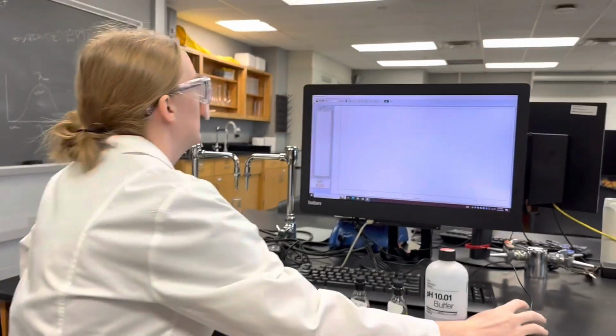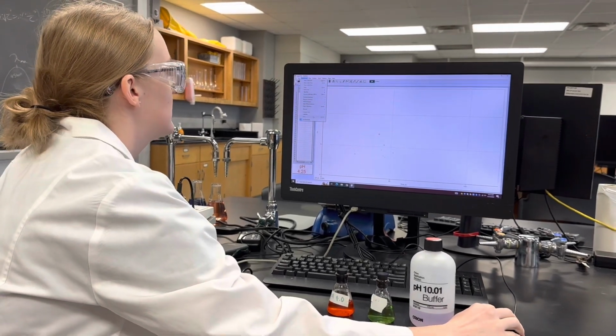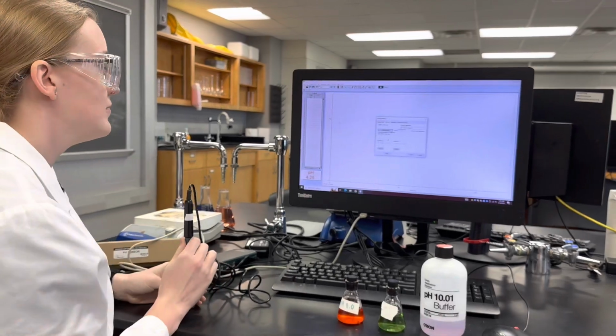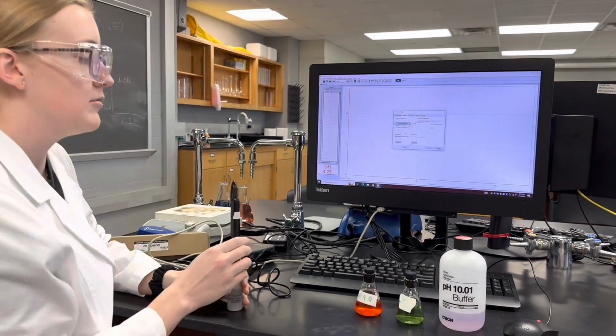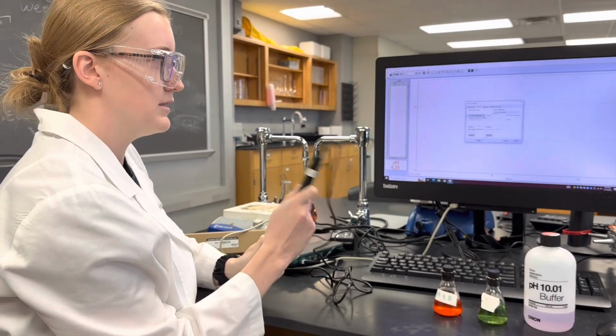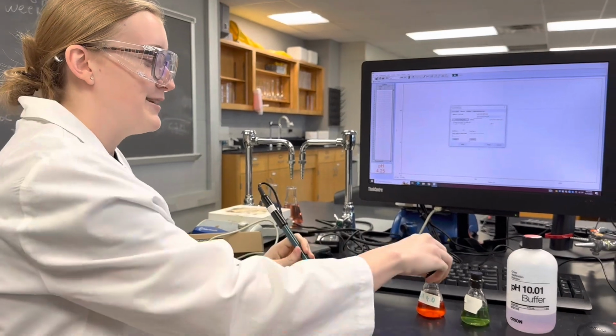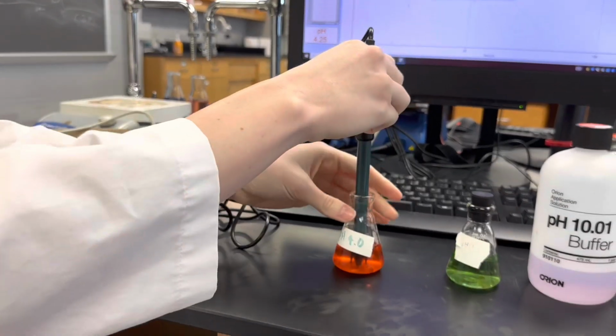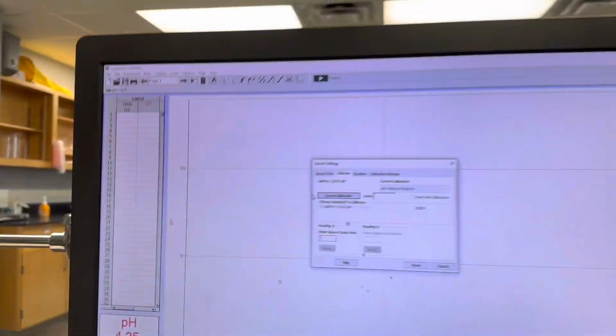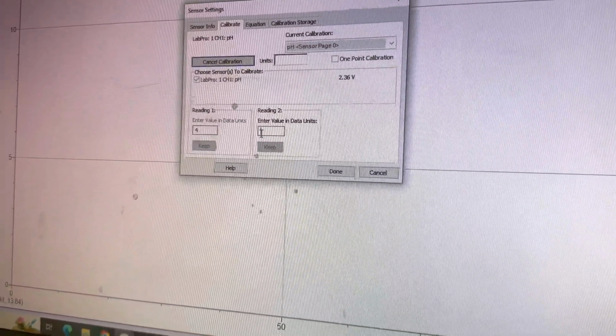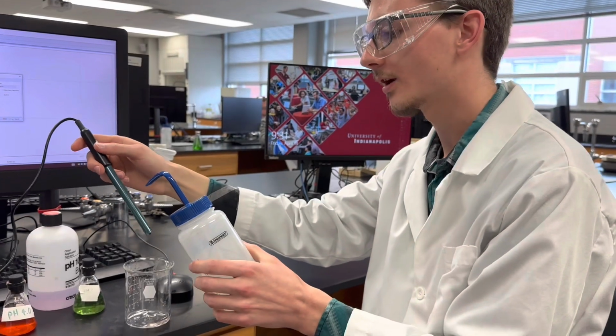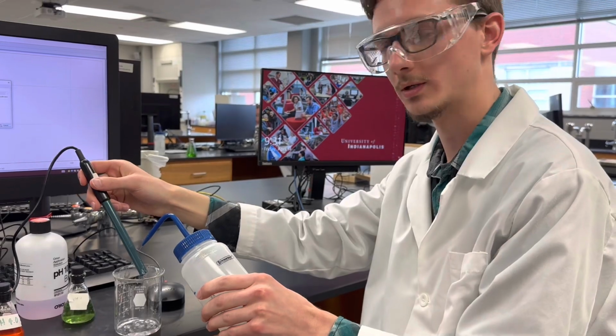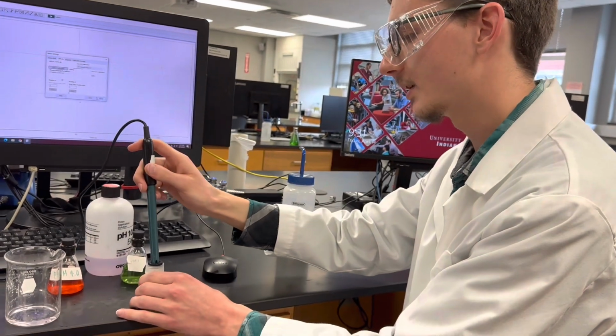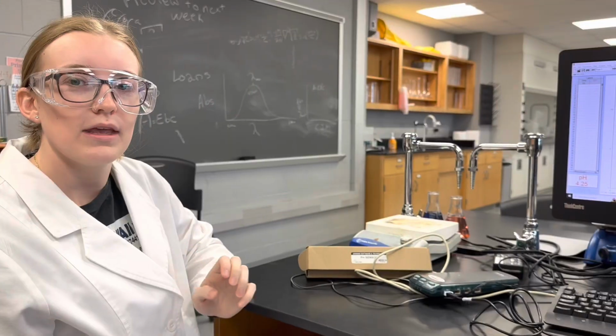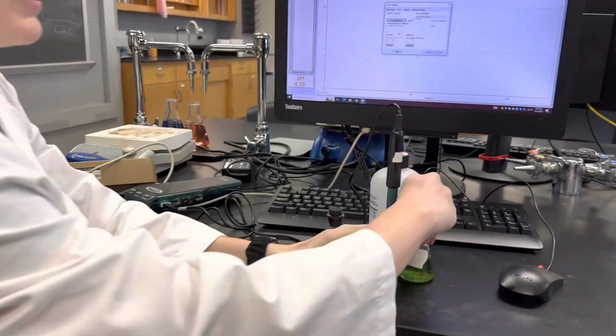So to calibrate, we will first need to go to Experiment, Calibrate, pH probe. So calibrate now. And then we'll take our probe out of the container of buffer and put it into our first pH buffer. Just give it a little stir, let it equilibrate. 4. Keep. After you take it out of every solution, rinse it with deionized water into a waste beaker. And whenever you're not using it, make sure you keep it in a buffer solution because the sensor has to stay wet. Once you have calibrated your first pH level, you will then calibrate it with your second pH level.